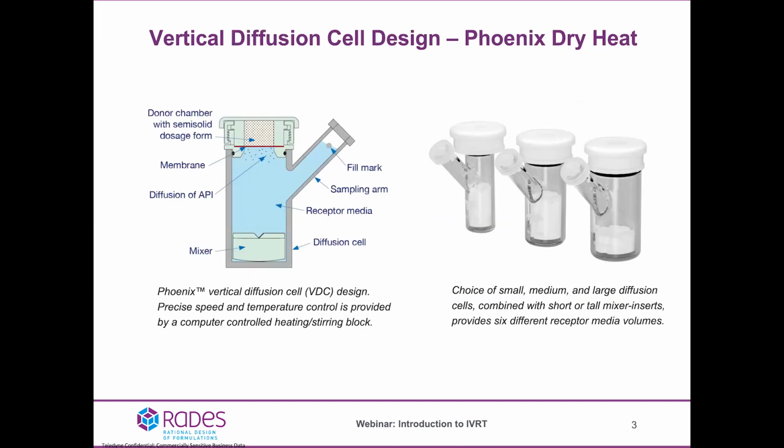Since this presentation is an introduction to IVRT, or in vitro release testing, it's important that you have a grasp of the tools and technologies available by Teledyne Hanson for semi-solid formulation development and API release testing. The component at the heart of our diffusion systems is our patented Phoenix dry heat diffusion cell, which we developed really as a great improvement over the traditional Franz cell, which was developed back in the early 80s.